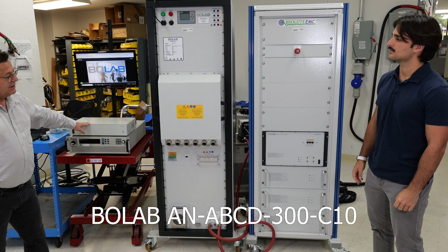So this is the main central unit where we connect the high voltage power supply and the 4-quadrant amplifiers, and the 4-quadrant amplifier and the high voltage power supply operate in serial connection. Such a 4-quadrant amplifier system is available starting from 40 amps, 80 amps, 120 amps. We are going up to even 2000 amps. That means an onboard charger that typically draws 30, 40, 50 amps can be done. DC-DC converters with typically 40 amps, heaters typically 30 amps, or even inverters going up to 800, 1000, 1500 amps can be done with such an amplifier system.